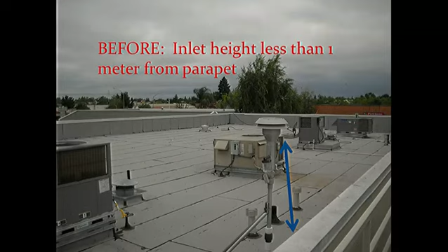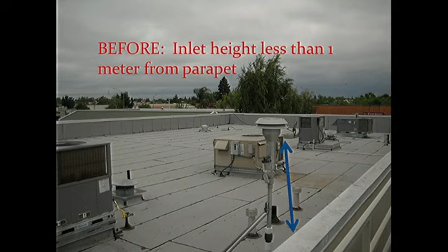Okay. This is how we normally go out and do measurements as the audit team. So we're double checking what you guys have. In this case, the inlet height was less than a meter from a parapet, and a parapet is basically a false wall, usually around roofs to hide HVAC equipment. In this case, we got a lot of before and after pictures. The operator was able to raise the inlet height so it was greater than a meter from the parapet.